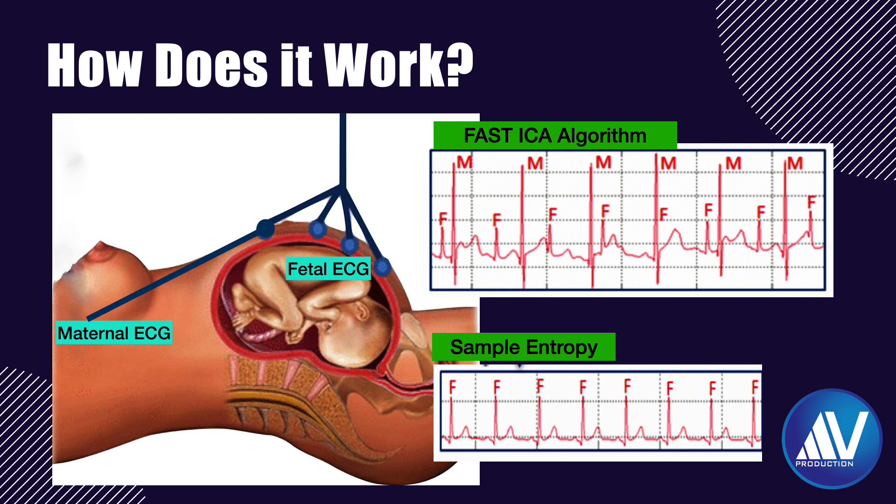The feasibility and accuracy of long-term trans-abdominal fetal ECG monitoring has been demonstrated by its variability being well correlated with scalp electrode recordings. Fetal heart rate detection using abdominal fetal ECG has proved more reliable and accurate than ultrasound, as fetal ECG has a higher ability to discriminate fetal heart rate. The intensity of uterine contractions is measured by electrical signals from the contracting myometrium via electromyography.